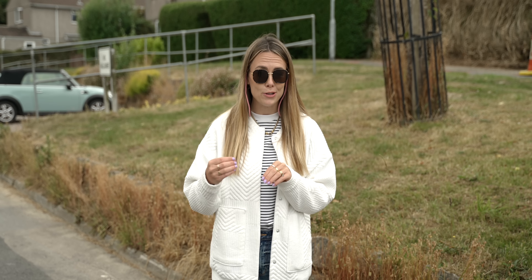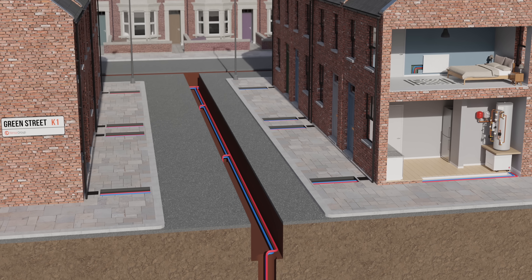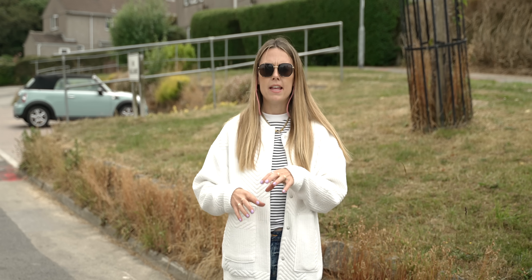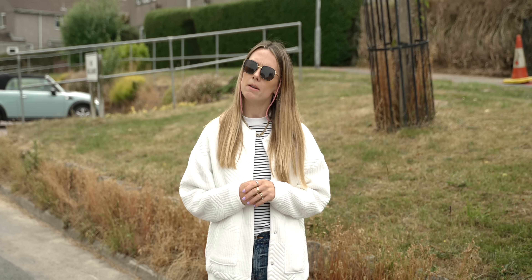In this project, instead of each individual home having its own individual borehole, there is in fact a network of 42 boreholes. I'm stood on top of one that goes 106 metres beneath my feet. There's a loop — an array — which sends coolant along this loop, absorbing heat from the granite below the ground, and it comes back up to the surface where it's turned from low grade heat into high grade heat in each home's individual heat pump. The really interesting principle here is diversification: the more heat pumps you have on the same system, the statistical likelihood of any one operating at its absolute peak load substantially reduces, meaning the overall design load for the whole system can be a little bit less — so Kensa doesn't have to dig quite as deep underground, saving money along the way.